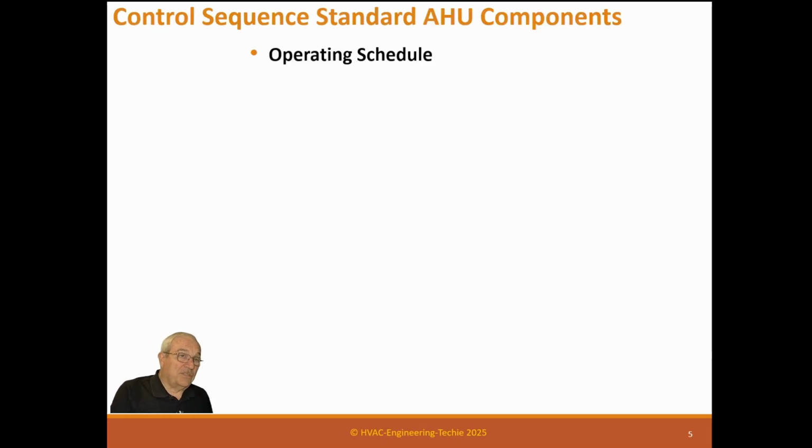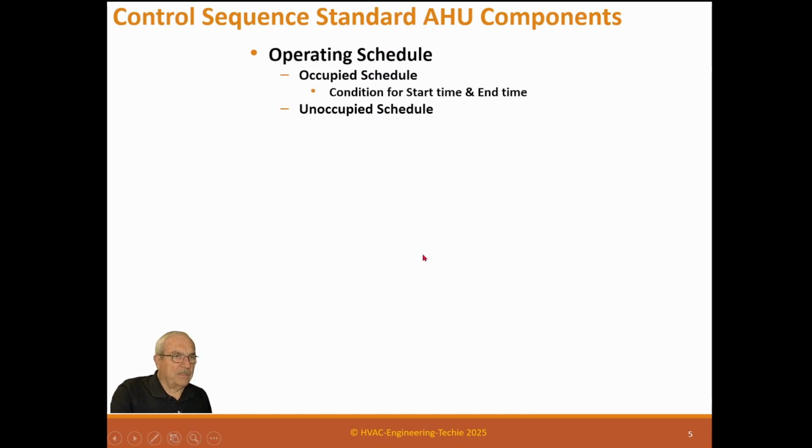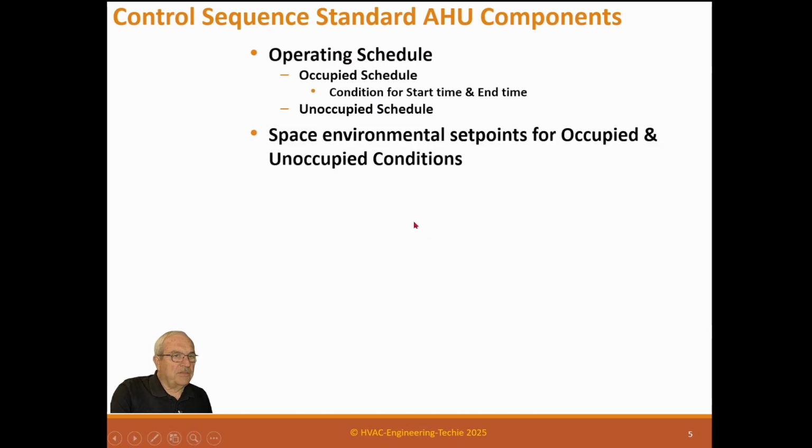All right, what's sequence standards for air handler components? We got operating schedule, occupied schedule, and unoccupied schedule. We get space environmental set points for occupied and unoccupied conditions. Remove set point dead band of 1 to 3 degrees.